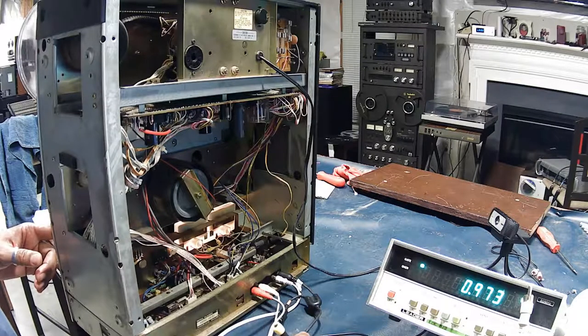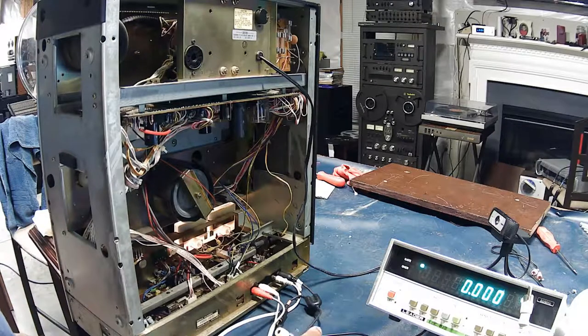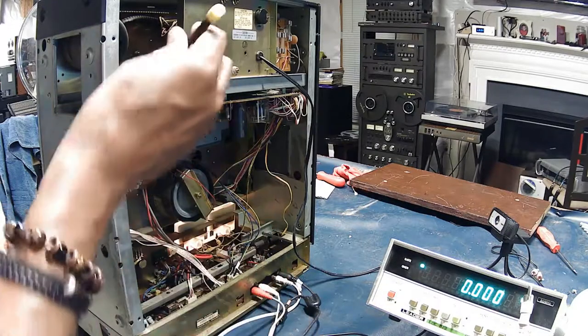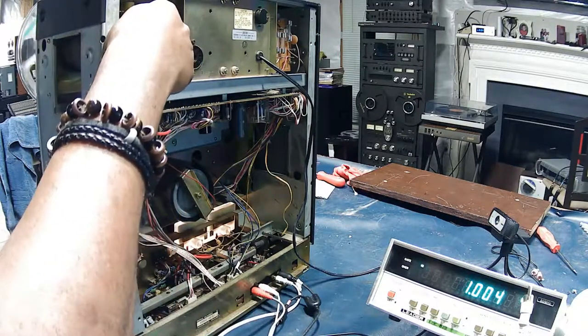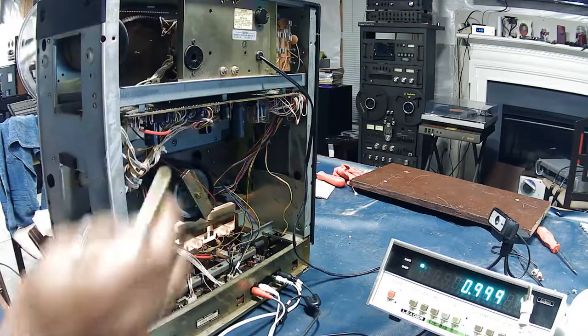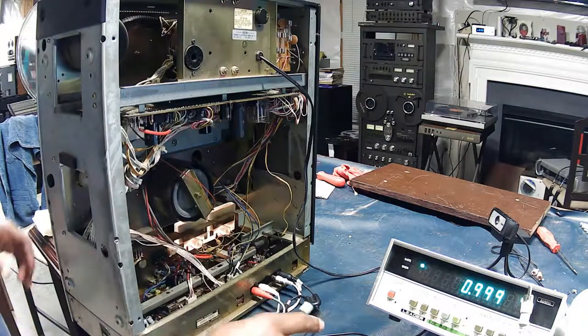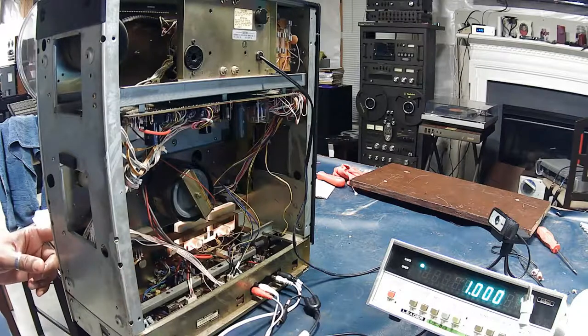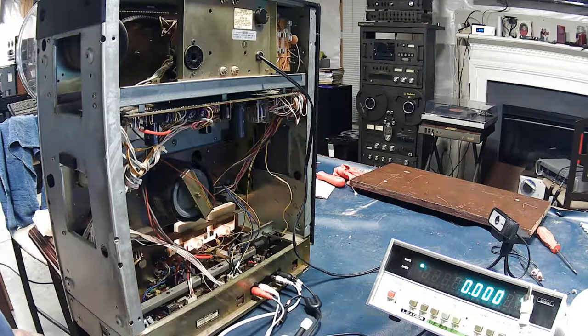Okay, so it looks like we're reading 973 hertz, and the tolerance on this one is 5%, so that translates to 50 hertz. So it is within spec, but I'm going to try to adjust it a little bit, get it closer to that 1000 mark. Okay, so we're going to leave it there.